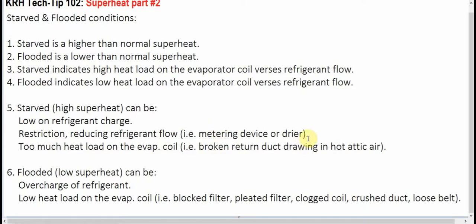We're going to discuss this in more detail in later videos, but at this point I just want to clarify that a restriction will usually be in the dryer or in the metering device. Then there's too much heat load on the evaporator coil. Now this can be caused by a broken return duct in the attic drawing in hot attic air. Typically that is what we find when we have a high load condition that causes a starved condition on the air conditioning system.